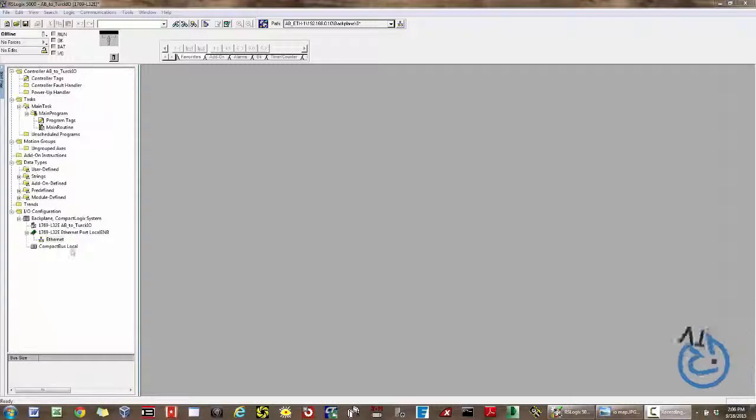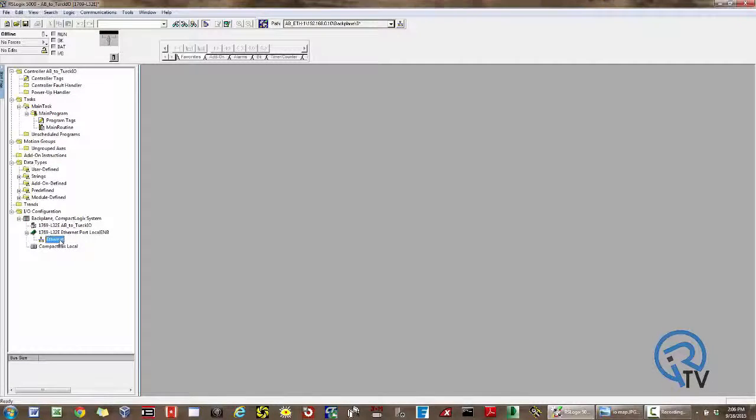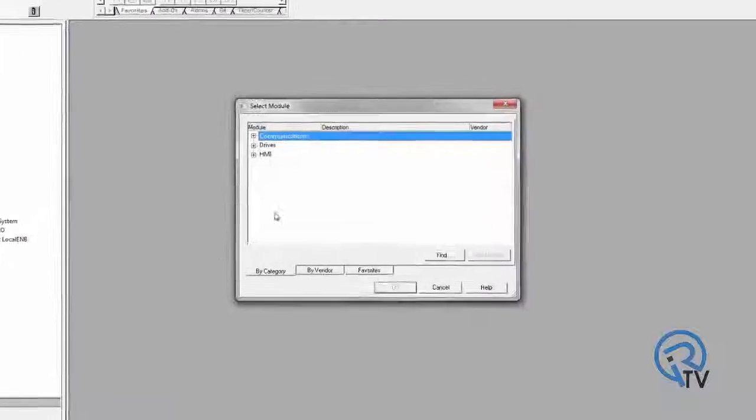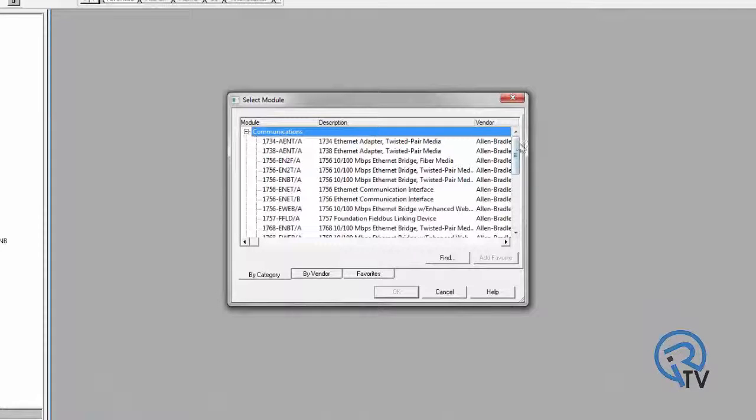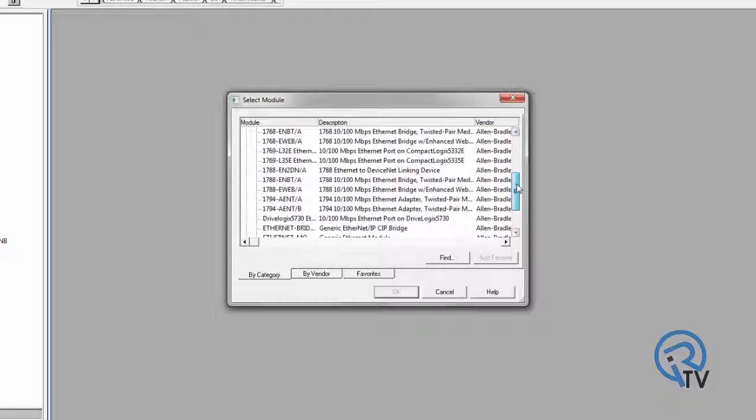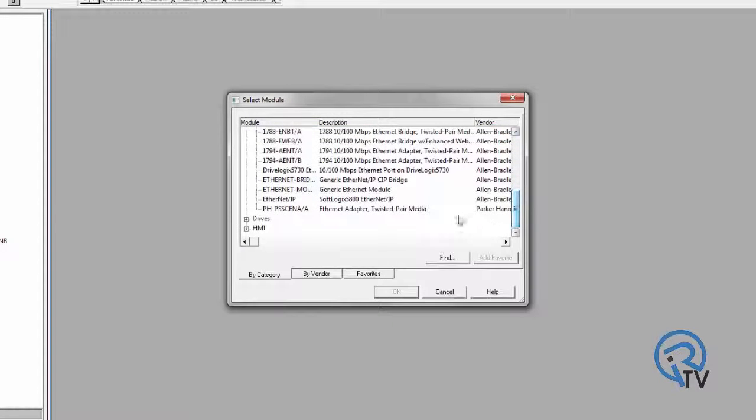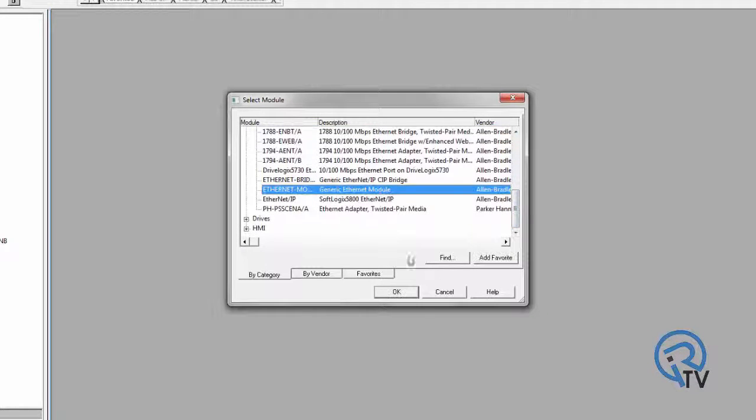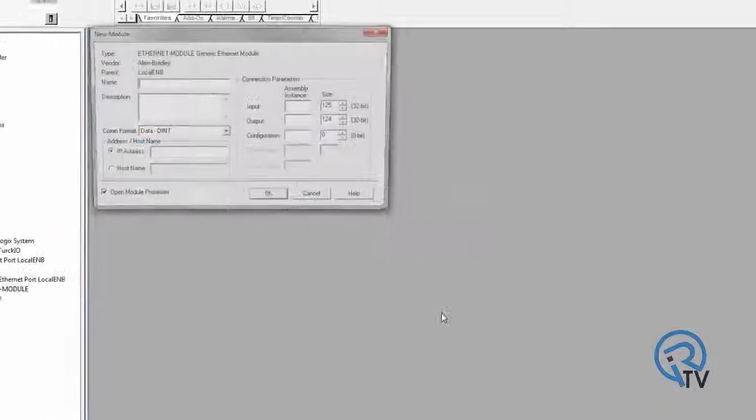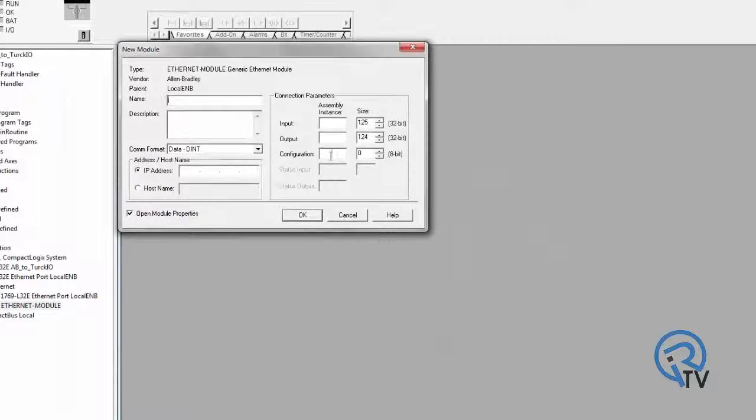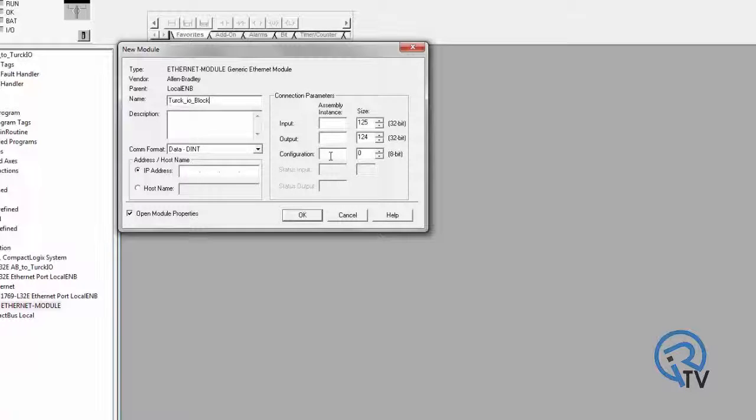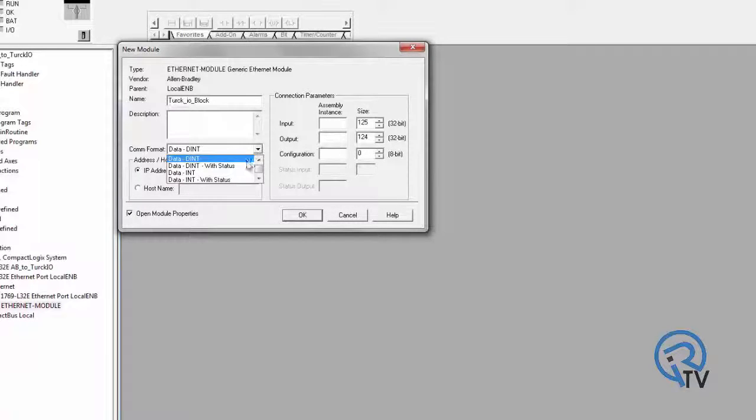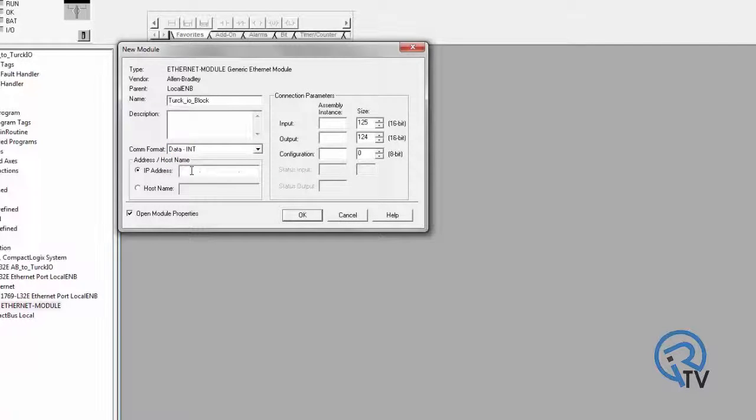Using Allen-Bradley software, right click Ethernet and select New Module. On Communications, find the Generic Ethernet Module and press OK. Give the block a name, typically this is based off the location of the block. And choose Data Integers to include 16-bit integers, then give it an IP address.